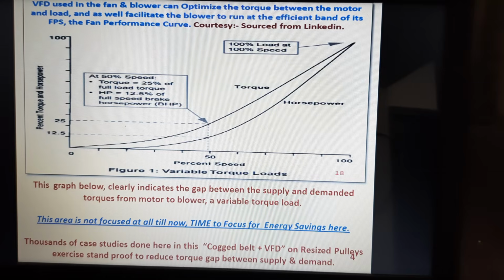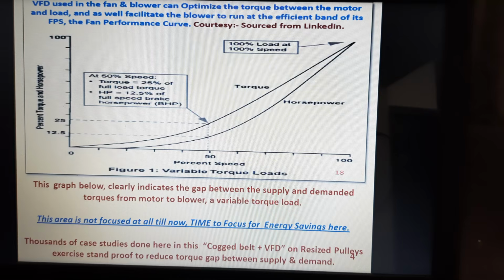This is an area which has not been focused on at all till now, and it is high time that we focus on this area and achieve energy savings instantly and affordably. Thousands of case studies have been done in this region, with cogged belts, VFDs and redesigned pulleys and belts, as proof of achieving this energy savings and reducing the torque gap between the supply and demand torque from the motor to the blower.